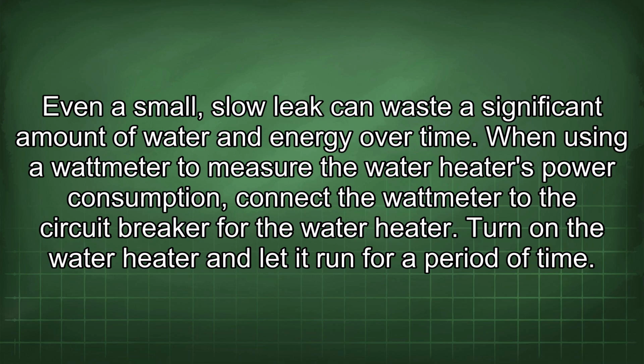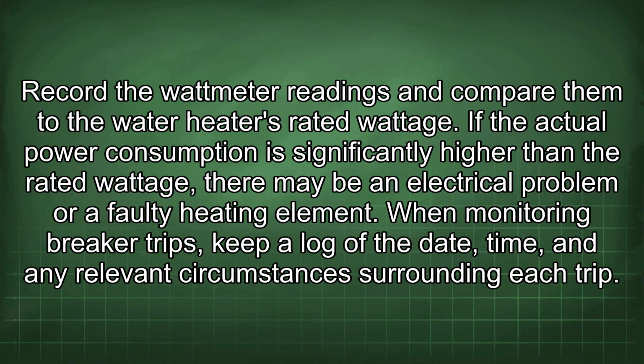When using a wattmeter to measure the water heater's power consumption, connect the wattmeter to the circuit breaker for the water heater. Turn on the water heater and let it run for a period of time. Record the wattmeter readings and compare them to the water heater's rated wattage. If the actual power consumption is significantly higher than the rated wattage, there may be an electrical problem or a faulty heating element.